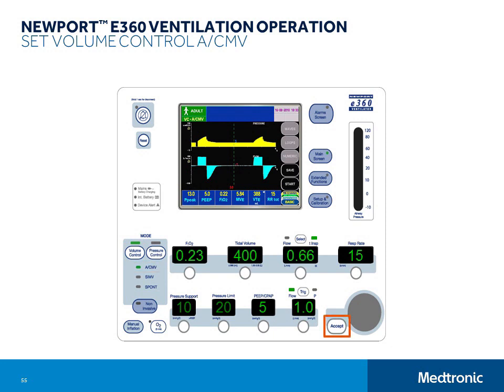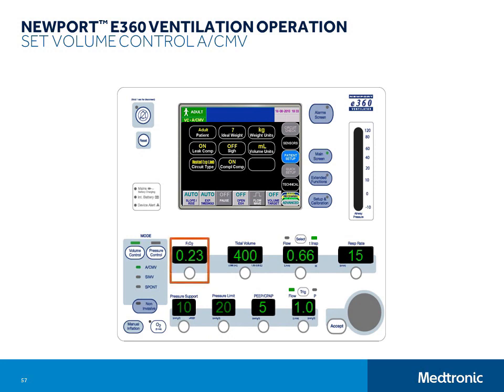Set FiO2, set tidal volume, set either flow or inspiratory time. Remember that you will use the select button to choose which one you want to set. Set respiratory rate, set PEEP CPAP, set trigger to flow or pressure, then adjust the setting. Then go to the GUI and set these settings. Set the flow wave to square or descending ramp for the volume control breaths. Set pause, and set the sigh.